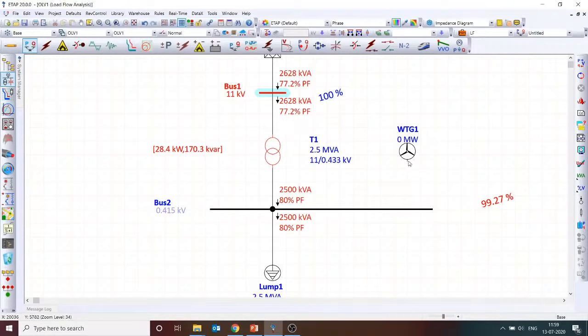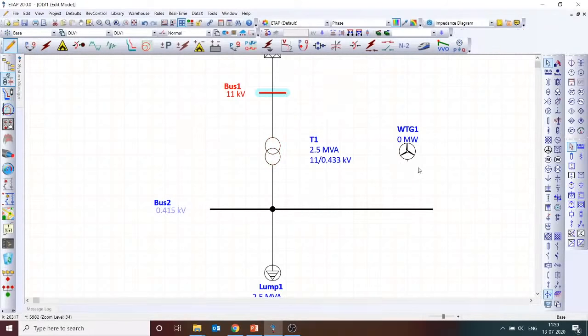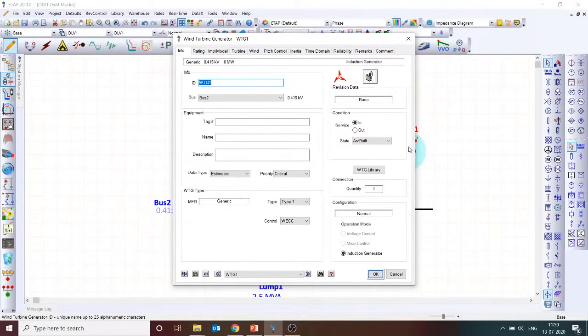Okay, after adding a wind turbine generator, you can see what's the power factor which happens at the grid. So I'm adding a wind turbine generator. Assume that industry has a nearby space and they have added a wind turbine generator. And you may appreciate the fact that you have four types of wind turbine generators, right? Type 1, type 2, type 3, type 4. Right. Type 1 is squirrel cage induction generator, type 2 is wound rotor induction generator, type 3 is doubly fed induction generator, type 4 is permanent magnet synchronous generator with a full converter. Right, there are four types.